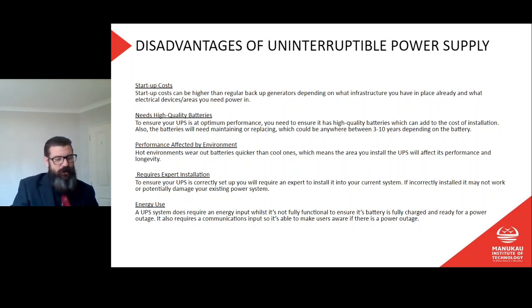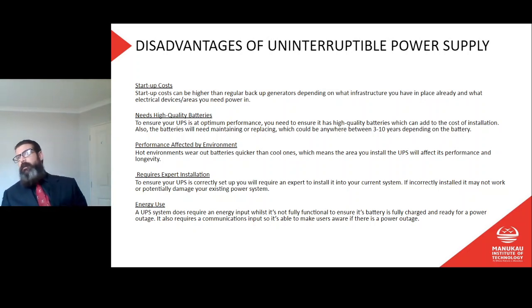I guess the point there is that a UPS will not, in most cases, be more expensive than a generator, but a generator would usually be in place to power the whole building, whereas a UPS is going to power like one computer or one room with computers in it. But if you wanted to do the same job, power the whole building or house with UPSs like you would with a generator, that's probably going to cost you a fortune. You're going to need a lot of UPS capacity.